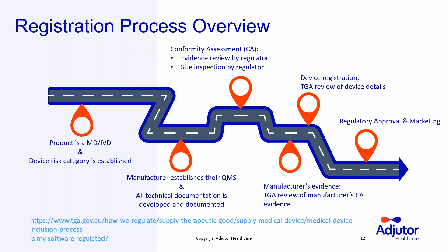As you would assume, the device risk category may differ among countries and may also change over time. In the next step, you establish your supply chain model and identify the legal manufacturer who will be responsible for the product, and also start working on the QMS to comply with the international standard ISO 13485. At this stage, you also start generating technical evidence to demonstrate that the product is safe and performs as intended. Next, a conformity assessment application is submitted. This can be either to a notified body, similar to Europe, or a regulator like the TGA. After you receive approval for the conformity assessment, the remaining steps are usually administrative processes.